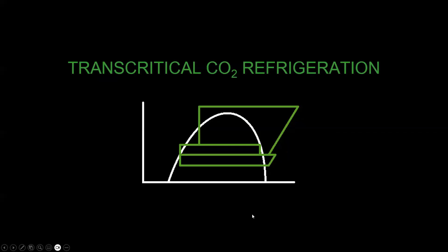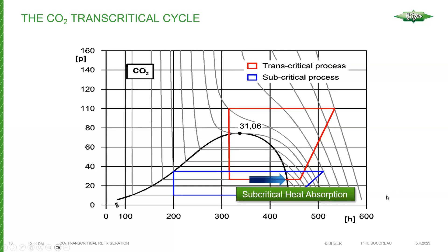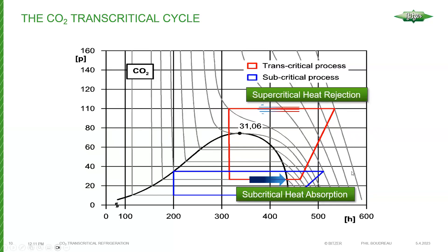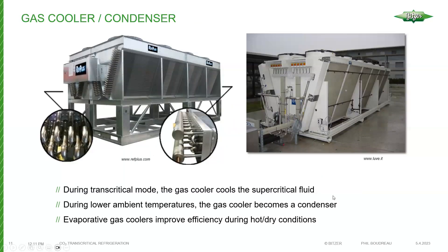Let's move on to transcritical CO2 refrigeration. In a basic single-stage transcritical cycle, the evaporator is in the two-phase region, so the evaporation process is subcritical. Whether it's a subcritical or transcritical system, the evaporator is always operating subcritically. What makes the transcritical system different is that we transcend the critical point into the supercritical fluid region. Heat rejection in transcritical is a bit different than what we're used to with HFC systems and ammonia.